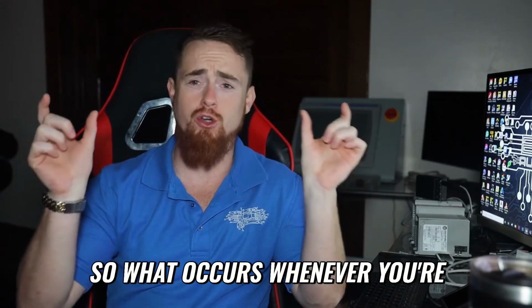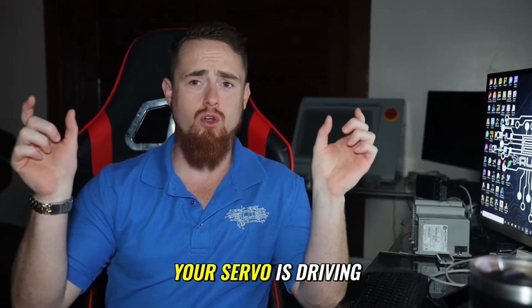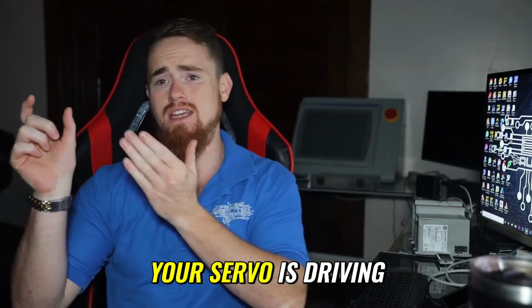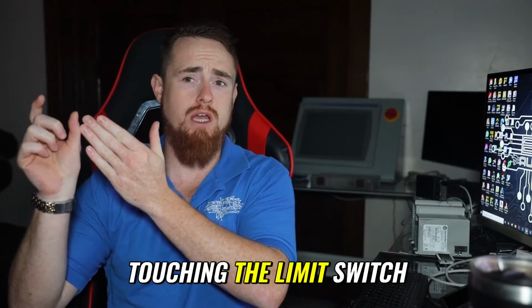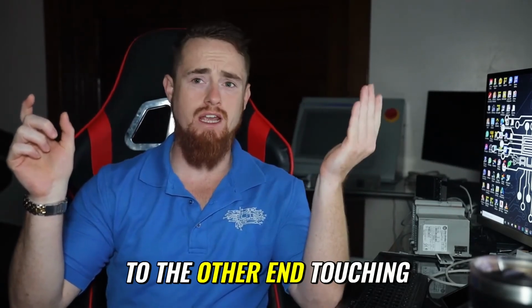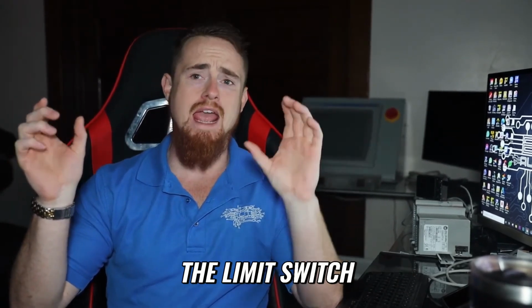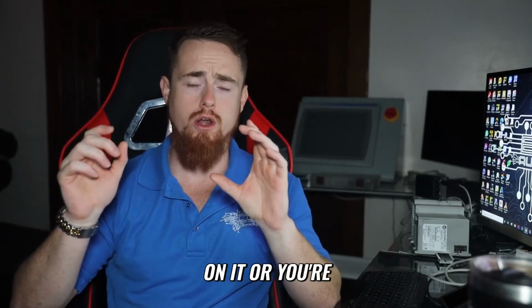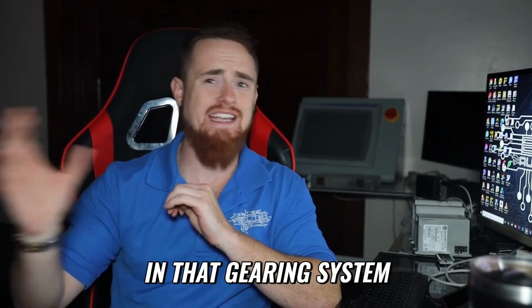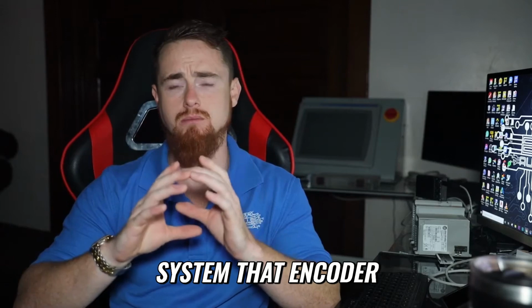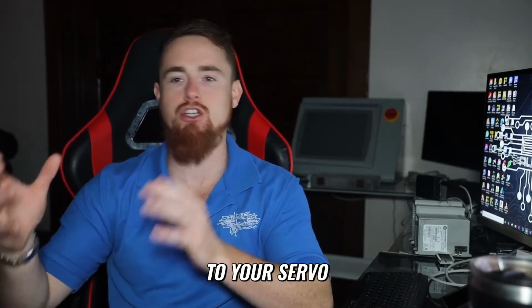So what occurs whenever you're doing your auto-calibration: your servo is driving down to one end, touching the limit switch, driving down to the other end, touching the limit switch. Your servo is going to have an encoder on it, or you're going to have it somewhere in that mechanical gearing system. That encoder is sending that data back to your servo.